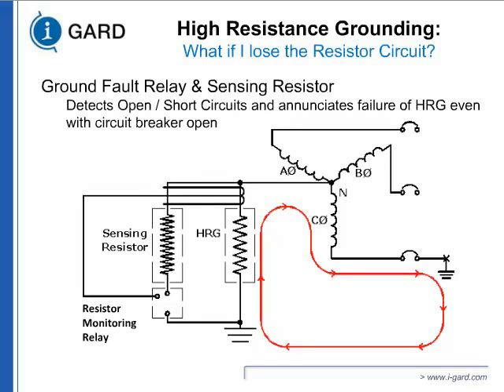So with this circuit, as long as control power is available in the relay circuit, you don't need main power on, so you can check if the circuit integrity is okay before you commission. Most of the systems available in the market only let you check when the fault happens and it didn't clear. So this gives you one option. Now you have protection against resistor circuit failure.